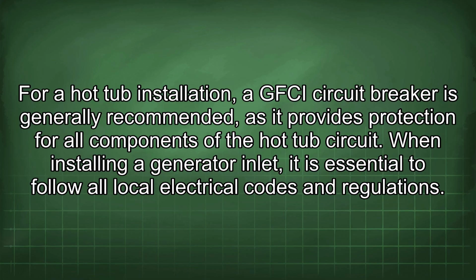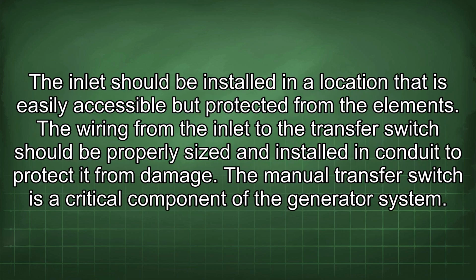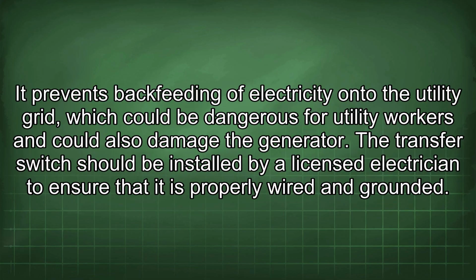When installing a generator inlet, it is essential to follow all local electrical codes and regulations. The inlet should be installed in a location that is easily accessible but protected from the elements. The wiring from the inlet to the transfer switch should be properly sized and installed in conduit to protect it from damage. The manual transfer switch is a critical component of the generator system. It prevents backfeeding of electricity onto the utility grid, which could be dangerous for utility workers and could also damage the generator. The transfer switch should be installed by a licensed electrician to ensure that it is properly wired and grounded.